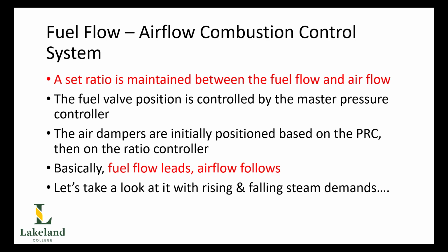It does not mean that. Airflow will still adjust first because that's safest from a point of view of combustion. However, from the control perspective, it's the fuel flow that sets the airflow. So because of that, it is said to have fuel flow as a leader and airflow as a follower.